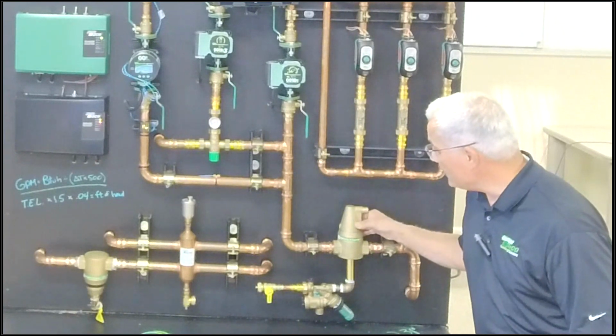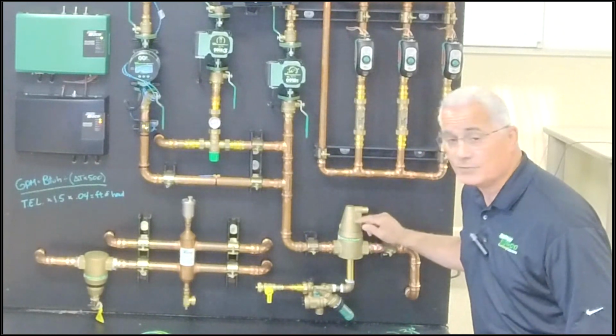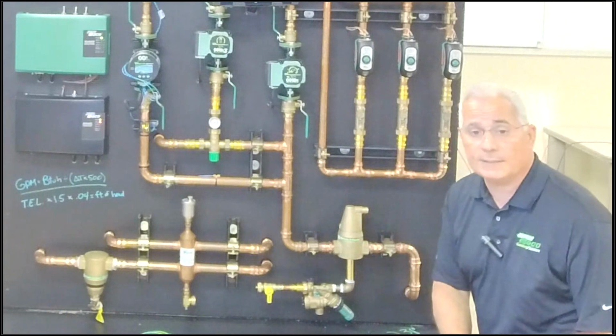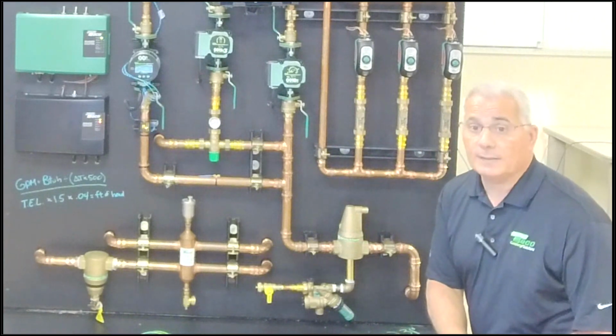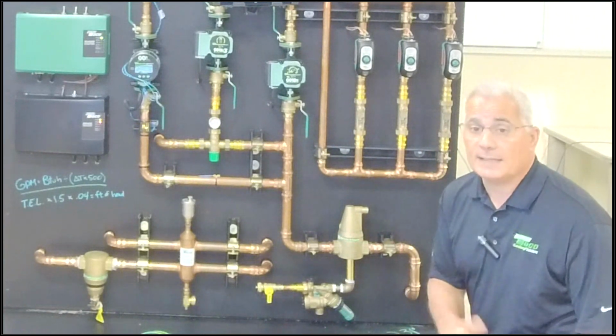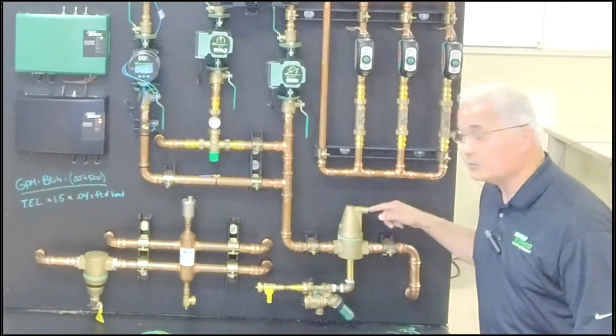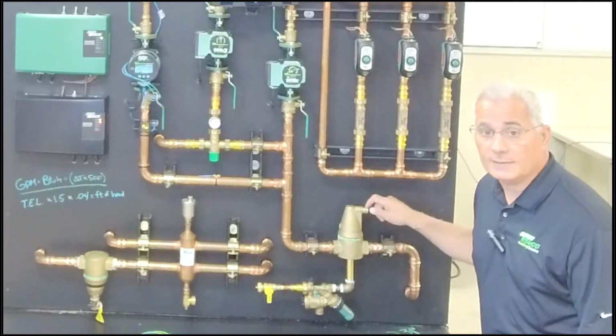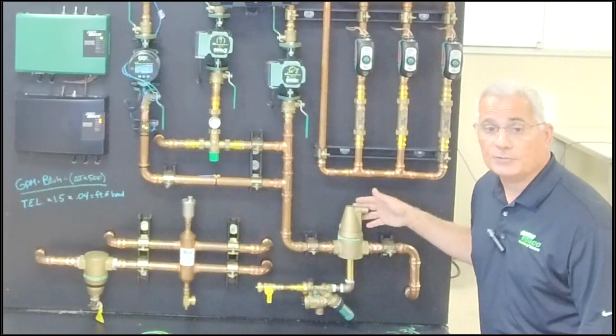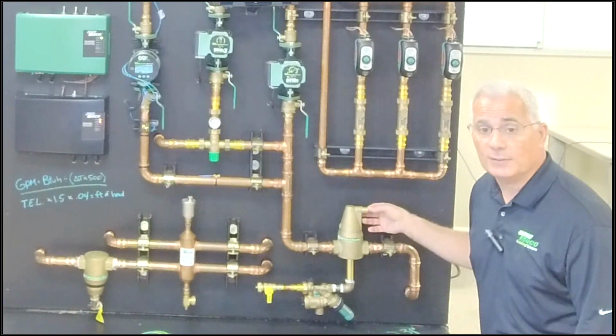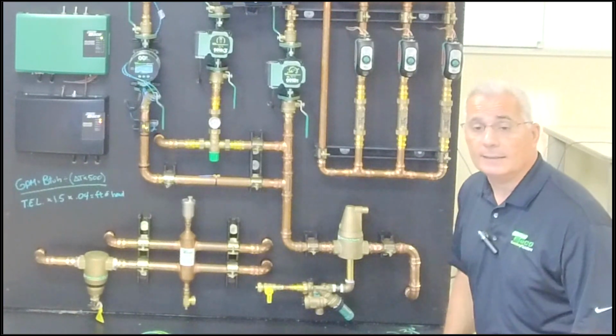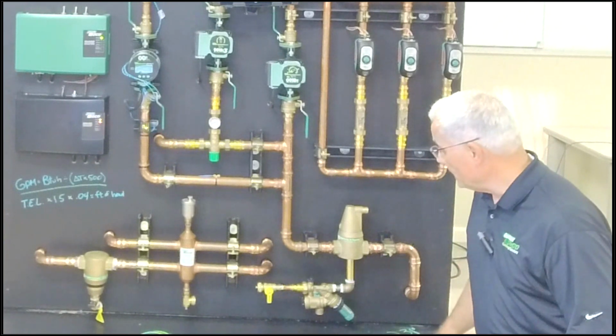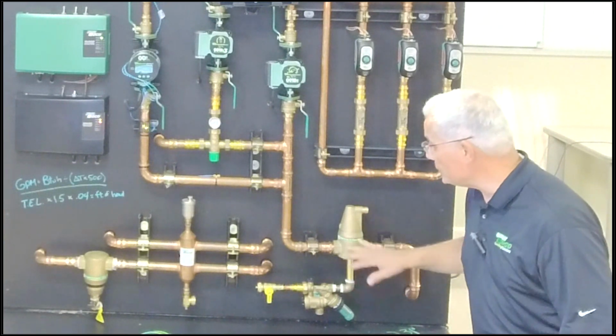The cone shape is on purpose. This is an air chamber, so we are never filled with water here. That does prevent a lot of leakage, so we don't see that on our side. We also have a shut-off valve built right into this. So once you've purged your system, if you choose to shut it off, you can shut it off. So this would be my point of no pressure change.